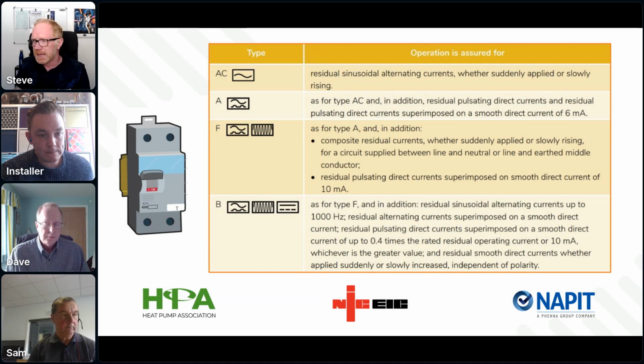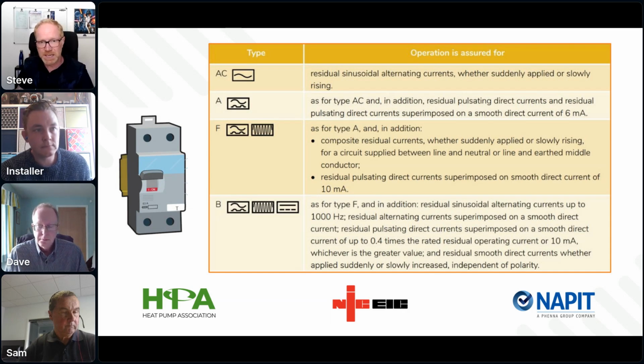Now, what we found in table 1 is that you've got the supply characteristics that will match that type of RCD. But it's also got further notes, and those notes give you a clue into what's going on. The manufacturer's instructions might not have that, but they'll have data sheets, and that's important. If you're using a reputable heat pump manufacturer, they'll have those data sheets, or pick up the phone or drop them an email and say, I need more information about the supply characteristics of your inverter. And like Dave's already mentioned, they'll all be different. Some will tell you one thing, some will tell you the other. We're going to come on to that later, but it's important that you know the supply characteristics. That's going to inform the designer's decision for what RCD to use. So table 1 is very important for that particular step.